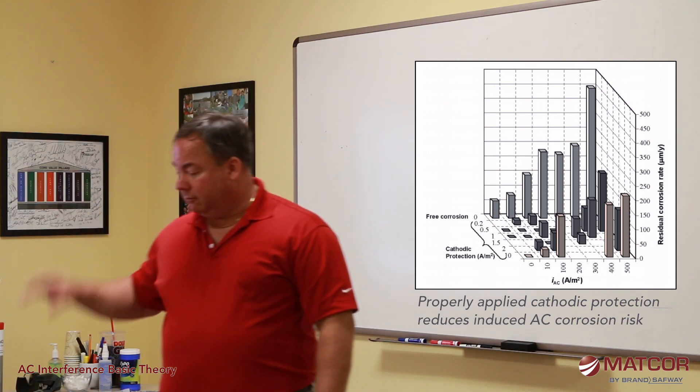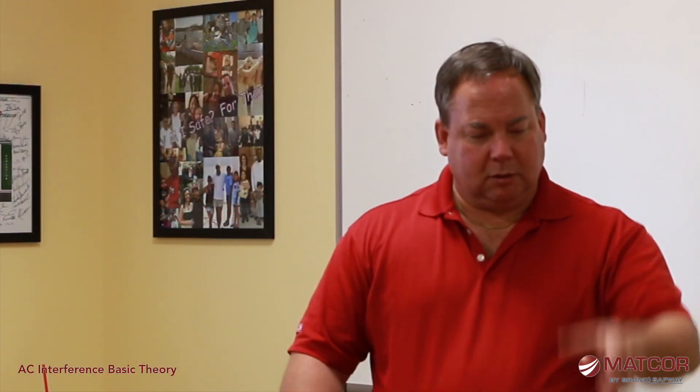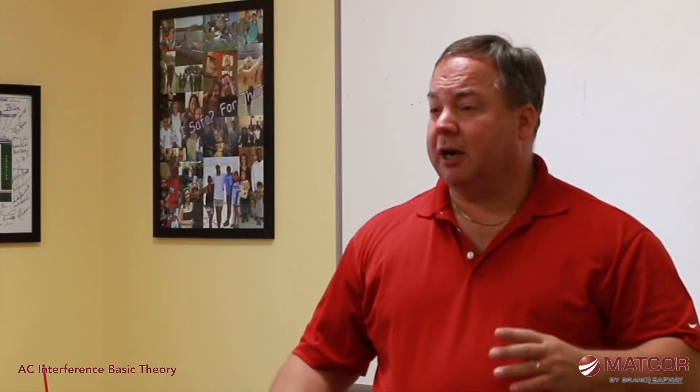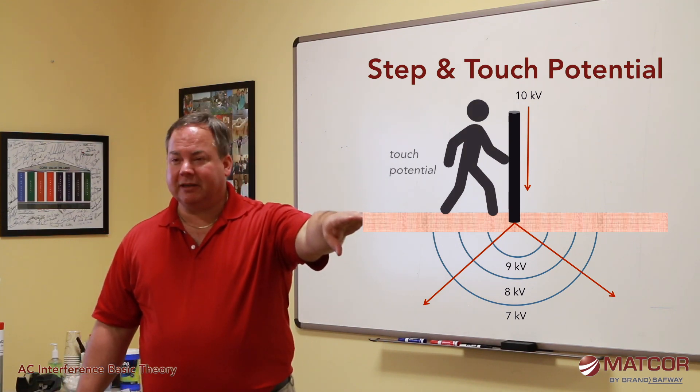The third threat of AC on pipelines is that you're picking up voltage on the pipeline, and at various locations the pipeline has appurtenances — valve stems, test stations — things that come above ground that somebody can touch. If the pipeline has accumulated a lot of voltage and someone touches a valve station or similar structure, they can get shocked — or even seriously hurt. We call that step and touch potential.